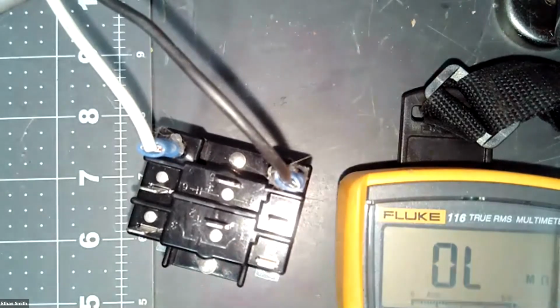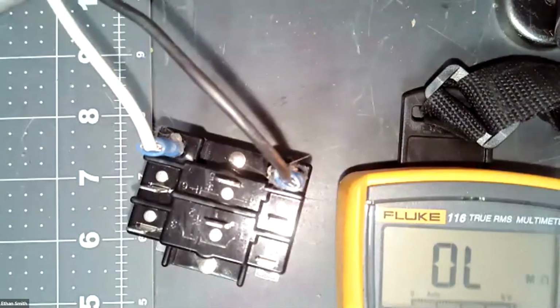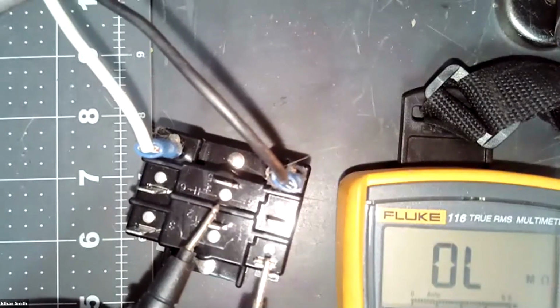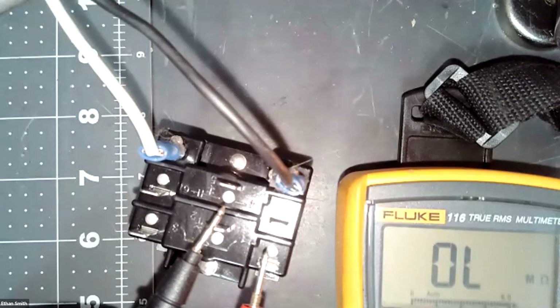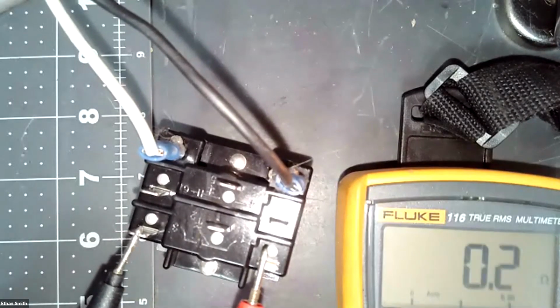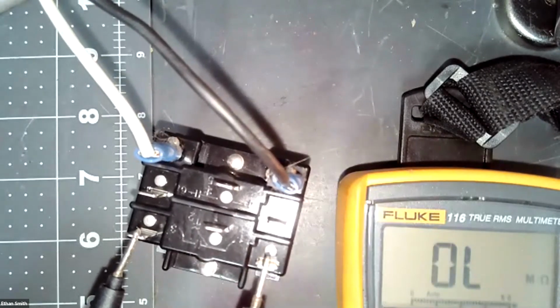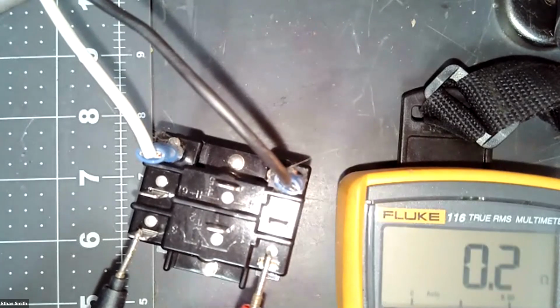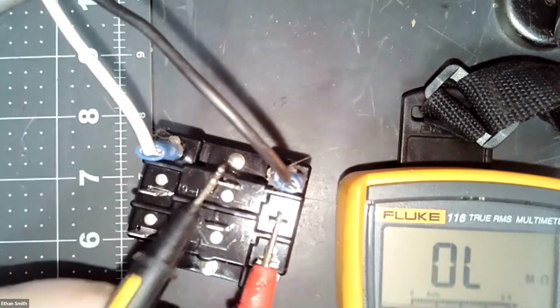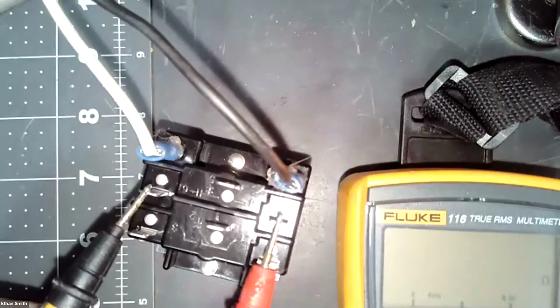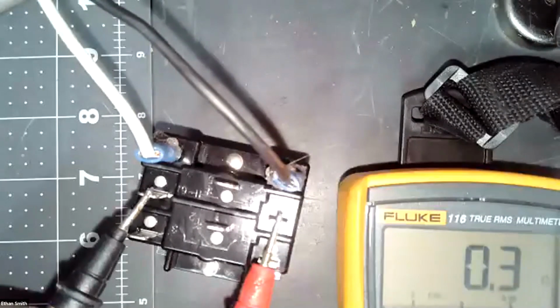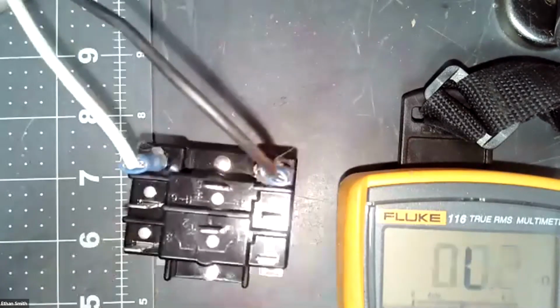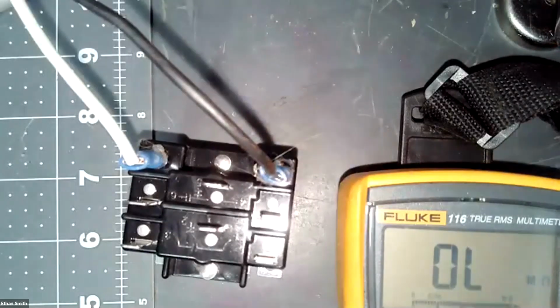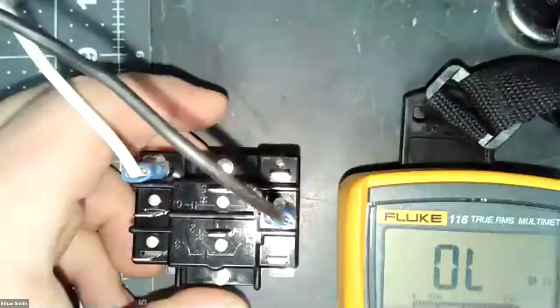Now, if I were to power this switch, we'll notice that my resistances across the switch have changed. Now I have an open line there, and I'm closed here, because now we've energized that normally open set of contacts. So now it's energized, it's normally closed. Same thing on this one. We've got open line here and normally closed there. Okay. So we can take this one step further. So we'll de-energize that relay. And let's put our power right here.